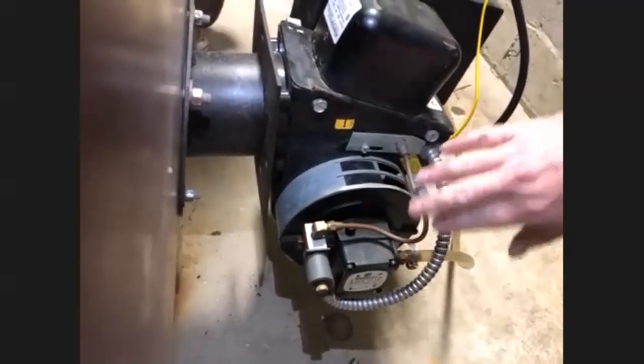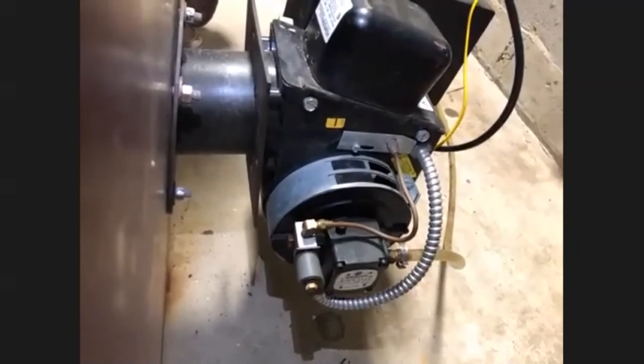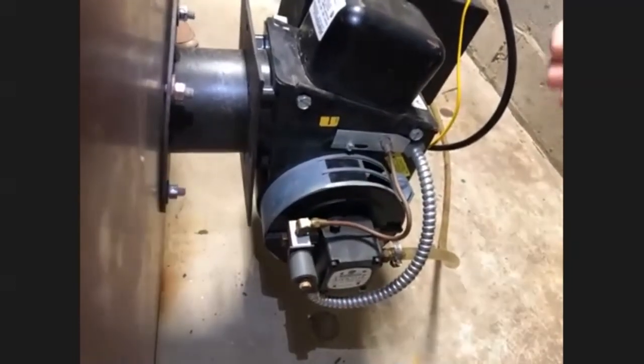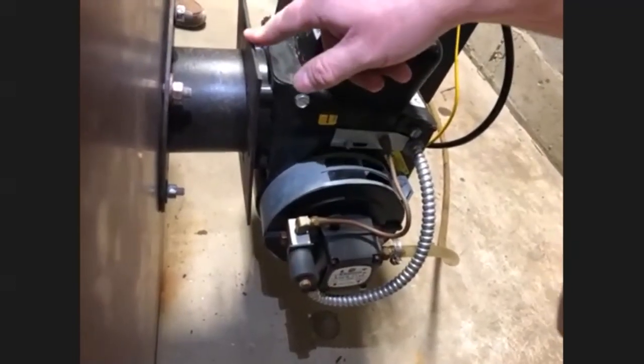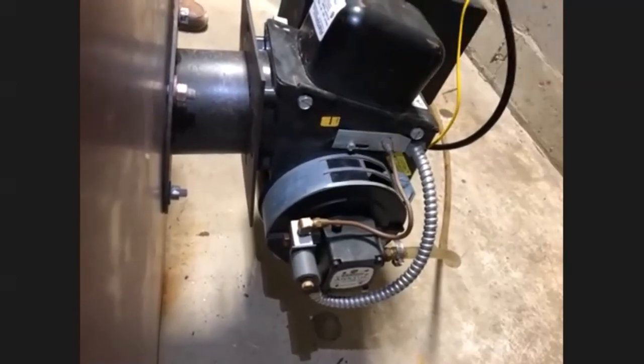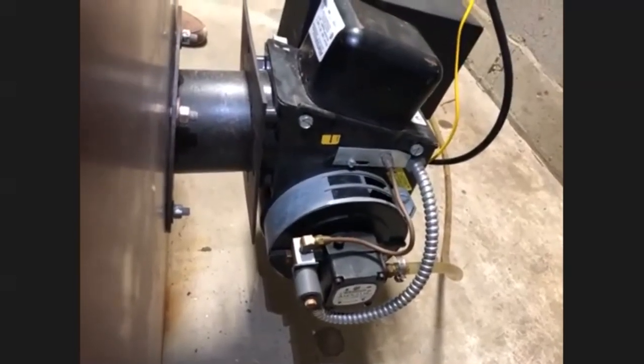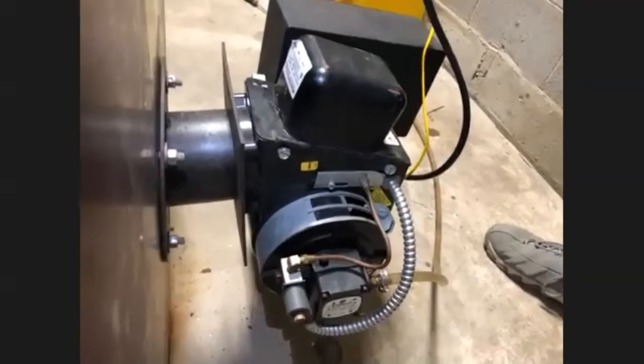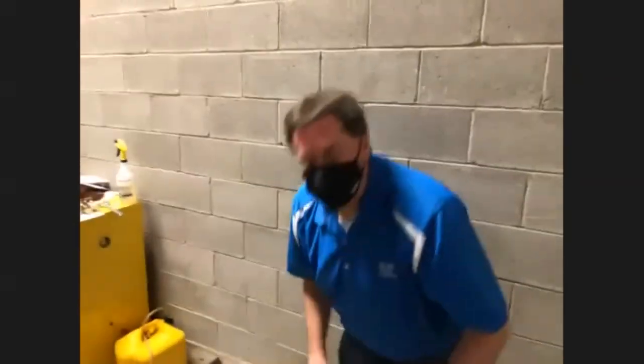you may have a blocked fuel line. You want to disconnect that, make sure it's cleaned out. Or the nozzle inside the gun assembly may be plugged up. You want to make sure your nozzle is cleaned off as well. Your fuel train, make sure that everything is cleaned out. Normally, you're going to find out whether your pump or your solenoid valve is faulted if you do not have any fuel mixture going through.